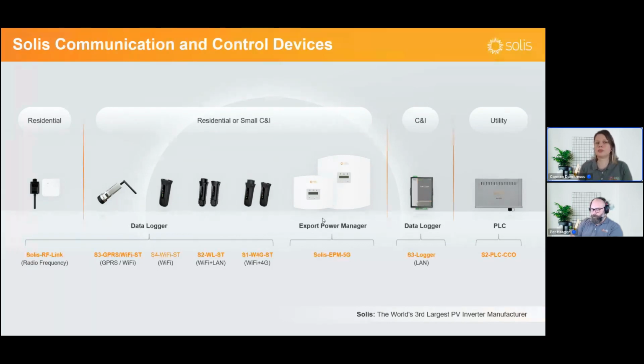So in order to do all this, you need one of the data logging devices that we offer. Definitely for the residential, the data logging sticks are the greatest. They can connect up to 10 devices. So 10 inverters with one dongle, you can connect at the same time through RS-485. Or you can have the EPMs with the data logging sticks. And for the C&I and utility, we have other options. We have the S3 data loggers, which will soon come out. And also we have the PLC CCO device, which allows inverters to communicate through the power lines, through power line communication in the utility projects, to achieve this.